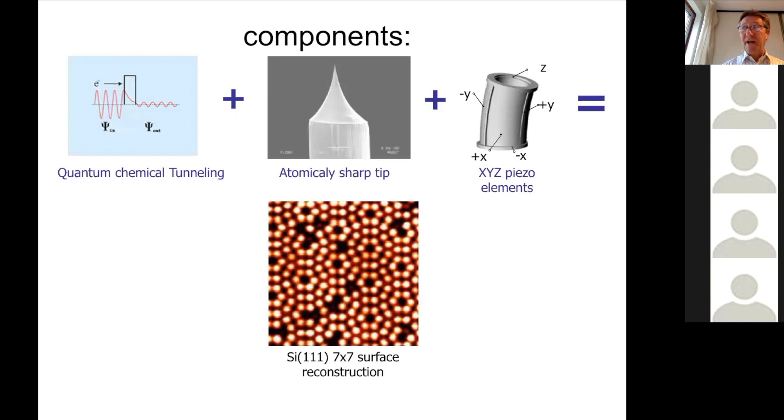Scanning tunneling microscopy is the first technique, and basically it is a combination of tunneling, quantum chemical tunneling that you know from quantum mechanics, together with a very sharp tip that is atomically sharp and piezo elements.